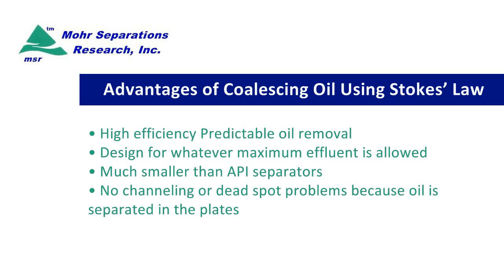We can design for whatever the maximum effluent is allowed. The requirement in the United States is usually that it meet the rules of the Clean Water Act, which is generally considered to be 15 milligrams per liter in the effluent, and that's certainly achievable with coalescing plates. Coalescing plate type separators are much smaller than API separators because they don't have to have the large residence time that API separators require.